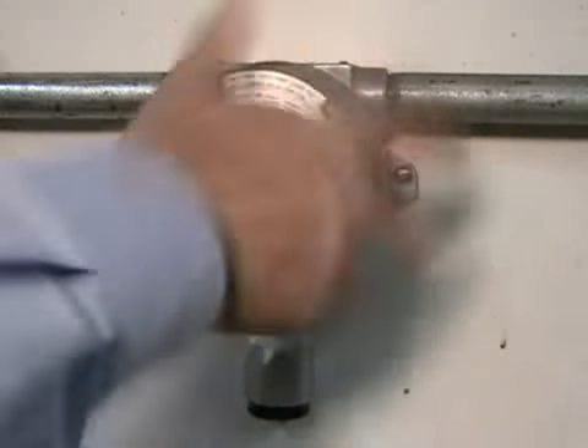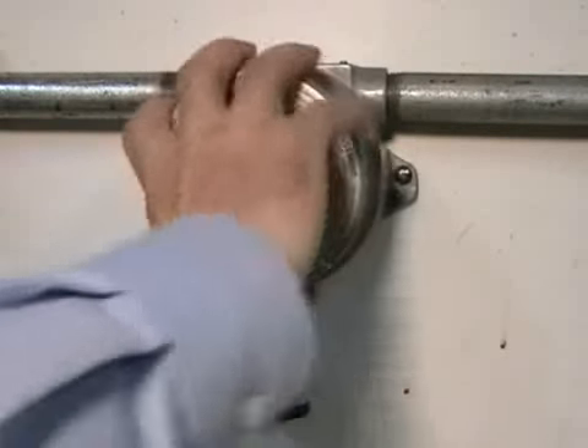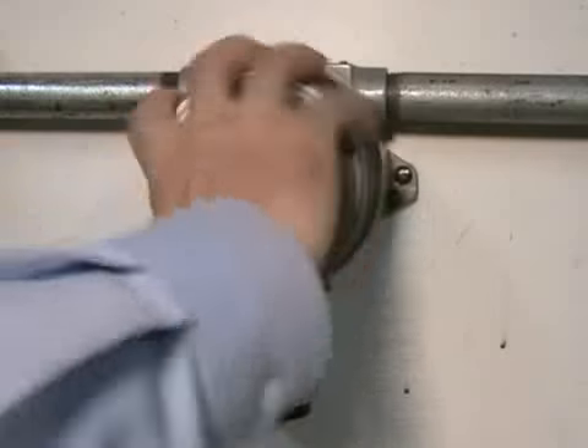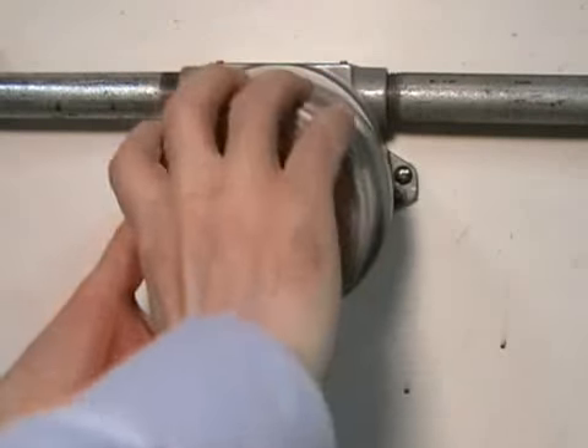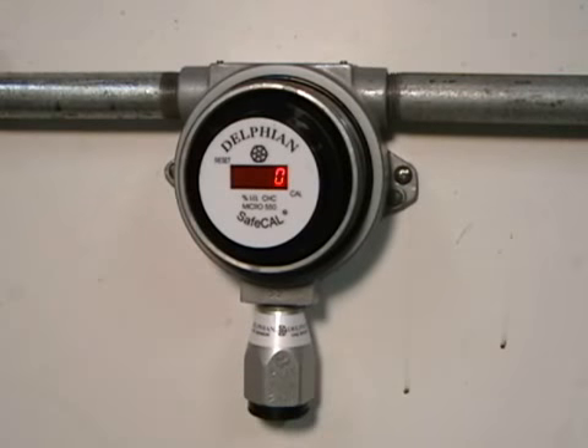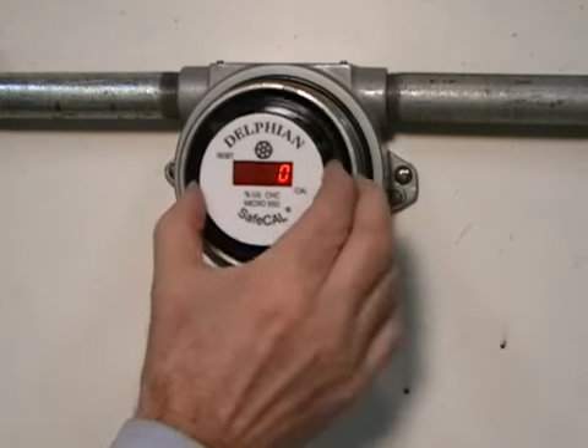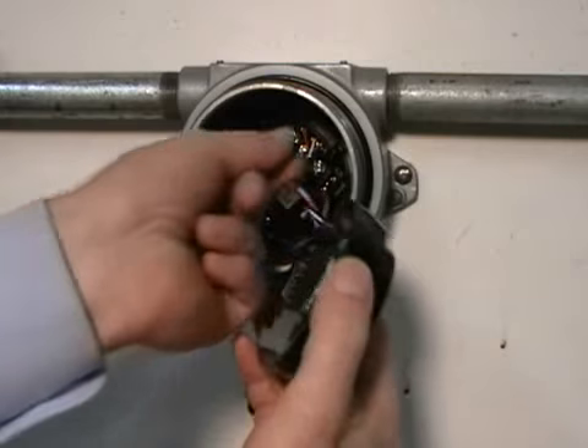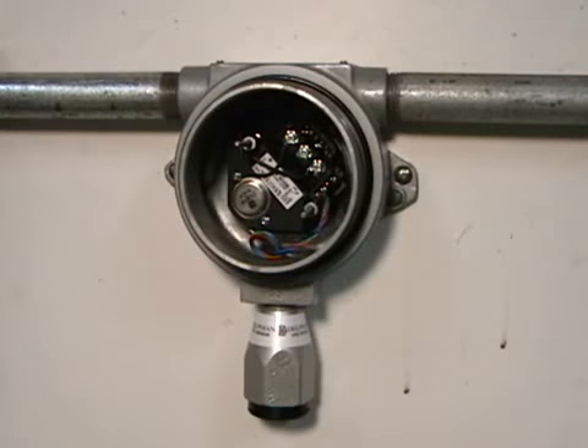Start by unscrewing the domed window explosion-proof housing cover, making sure that you declassify the area if you're working in a Class 1 hazardous location. Once opened, remove the SafeCAL by simply pulling the 5-pin connector off the transmitter located at the bottom of the housing.